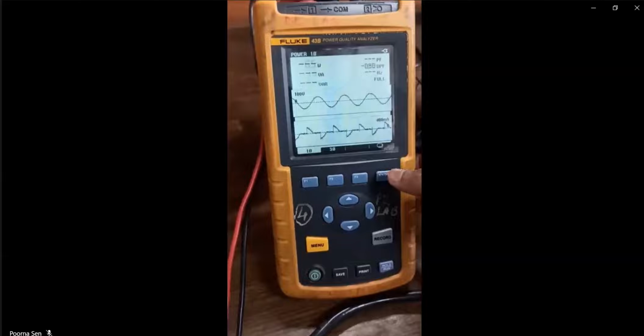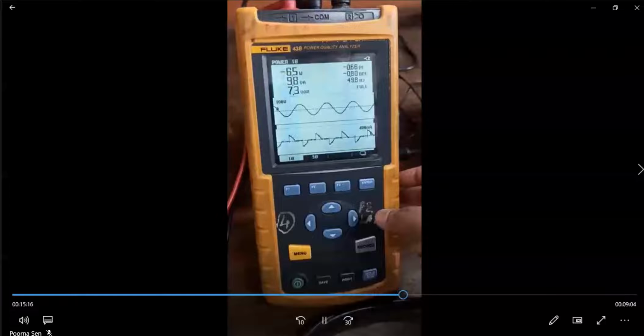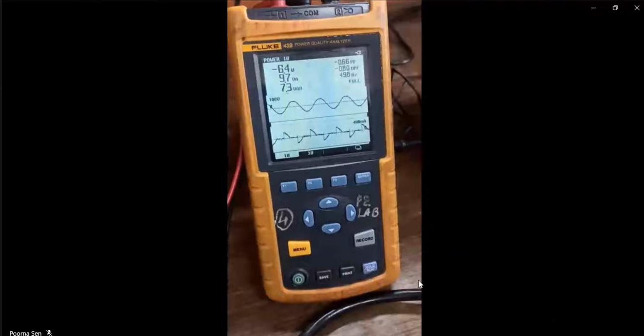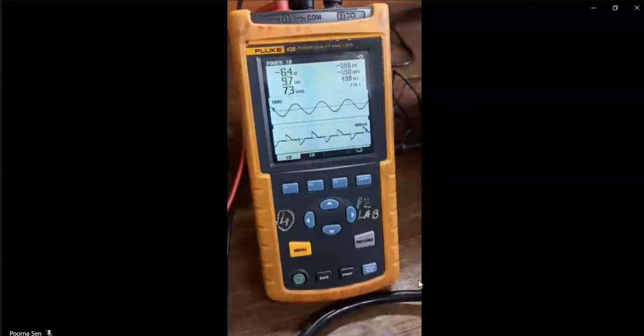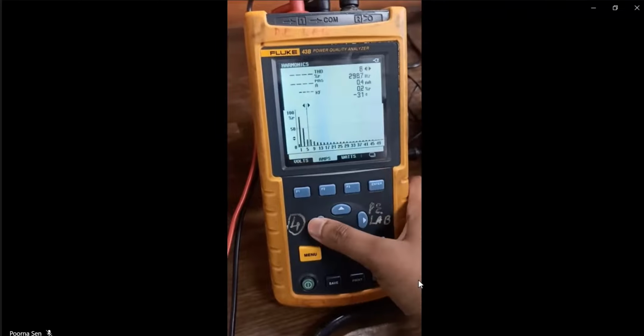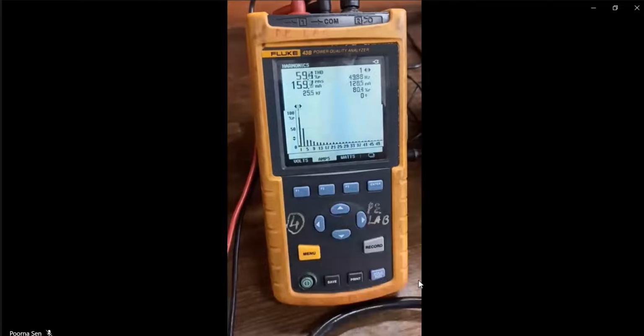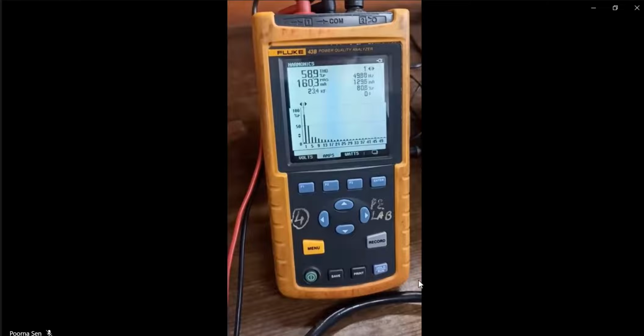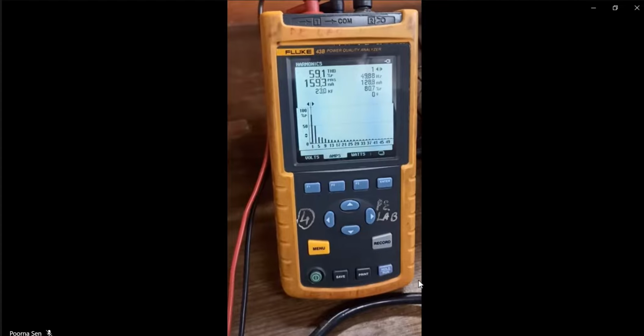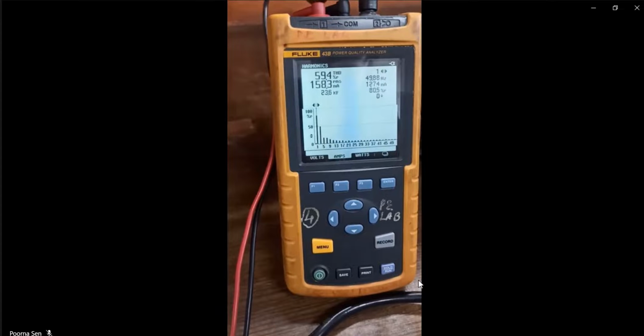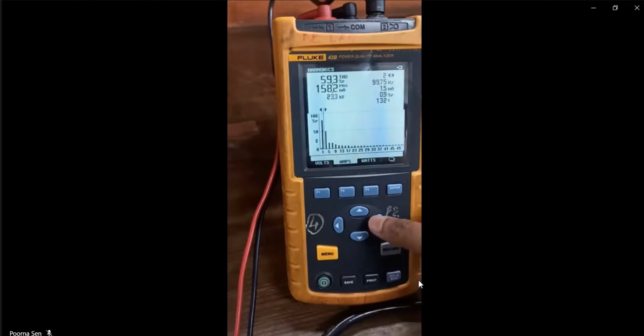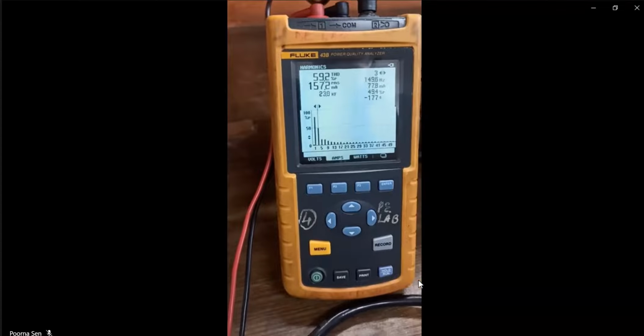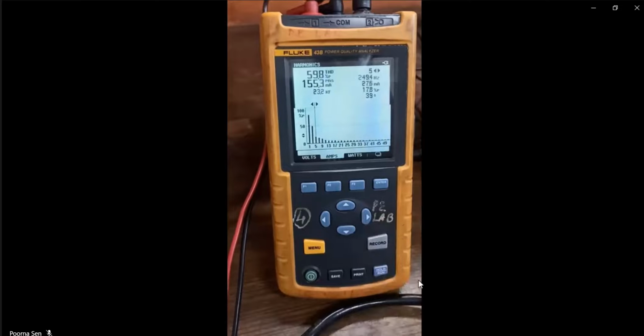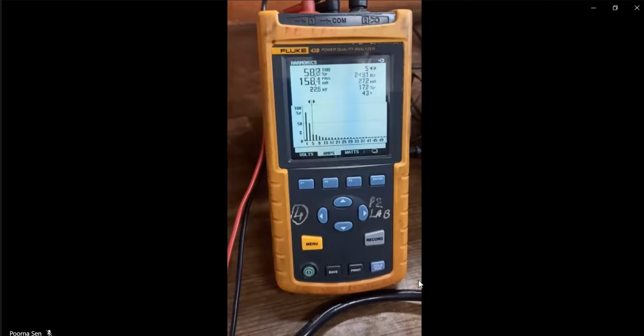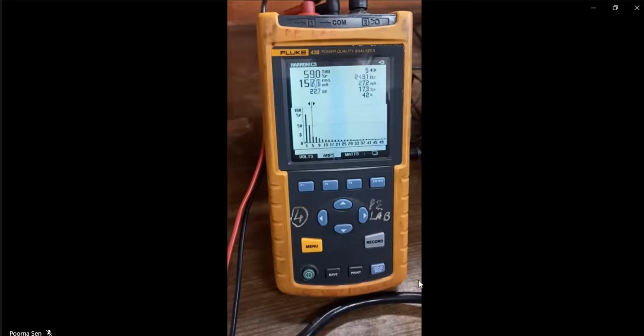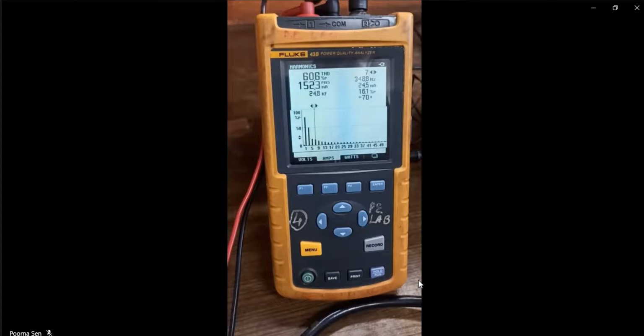Power is 6.5 watt. Reactive power is 9.8 volt ampere. Power factor is 0.66. DPF is 0.8. THD is 58.8%. First harmonic is 127.2 milliampere. Third harmonic 77.6 milliampere. Fifth harmonic 27.2 milliampere, and seventh 24.7 milliampere.